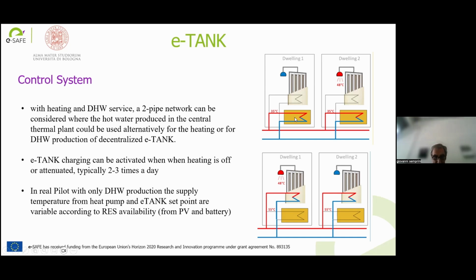In the real pilot of Catania, with only domestic hot water production, the outlet temperature from the heat pump and also the tank set point are changing based on the availability of renewable energy source from photovoltaics and batteries. Then we consider the possibility to change the supply temperature according to availability of free energy from the photovoltaic system.